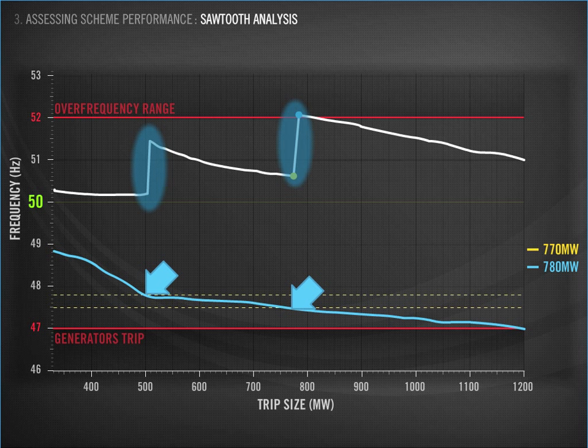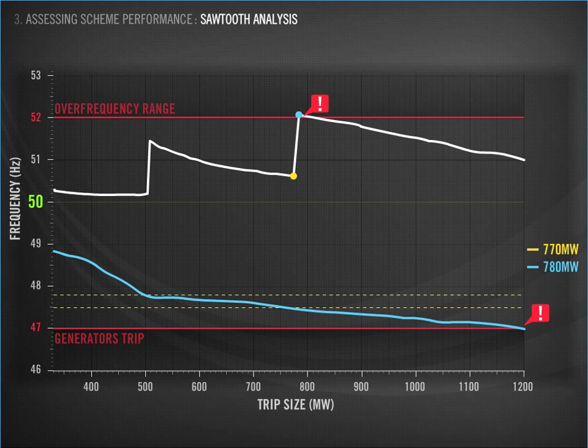Viewing the events in this way allows us to focus on areas of concern. In this example, an event of around 800 MW is going to result in overshoot above the 52 Hz limit. A larger trip size of 1200 MW results in the frequency going below 47 Hz. Both of these scenarios result in non-performance, which we want to avoid.